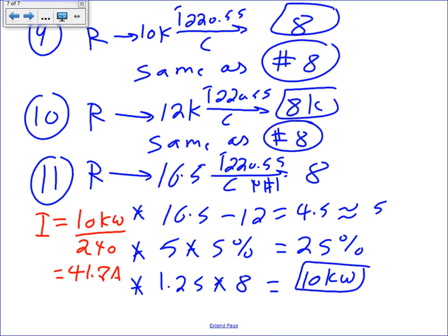41.7 amp. Okay, cool. No problem, Chad. Then you take the 41.7 amp, take it please to 310.15 B16 under the 60-degree column. What's the conductor size? Number 8. Can number 8 get us there?